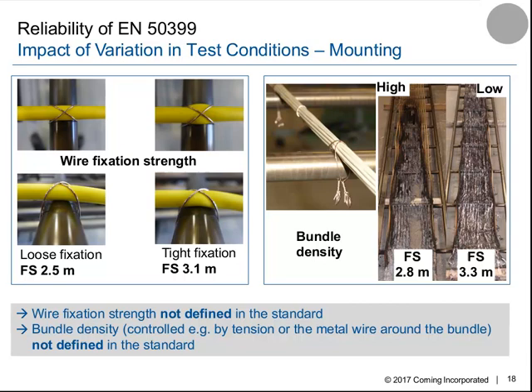Let's have a look at the bundle density. If we increase the density by tension, for example, or by adding an additional metal wire around this bundle, we can increase this bundle density. And what we found is that with an increased bundle density, the flame spread is decreased by approximately 50 centimeters. But again, the bundle density is not defined in the standard. So at this point, one really has to mention that for mounting, there are some parameters, some conditions still not well enough defined, which leaves room for variations.